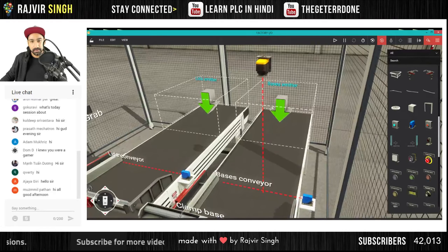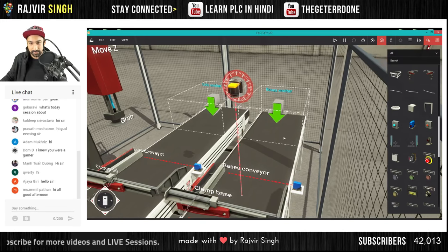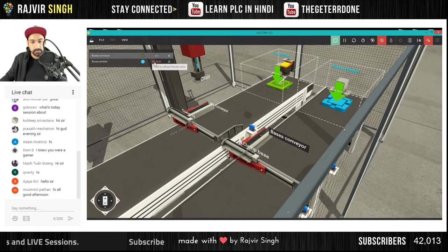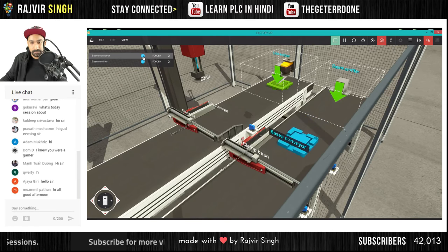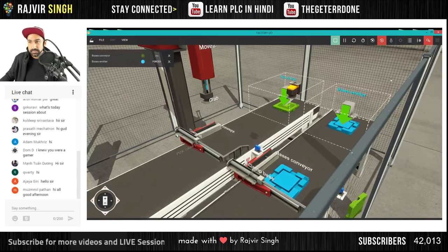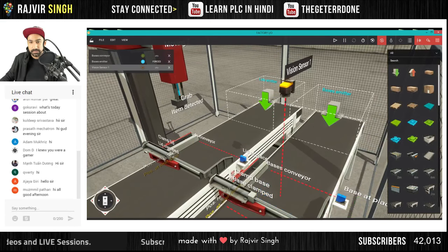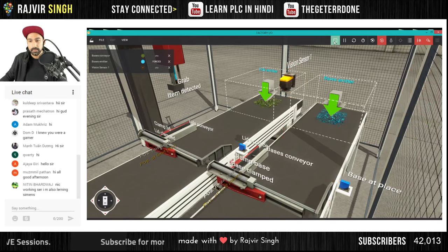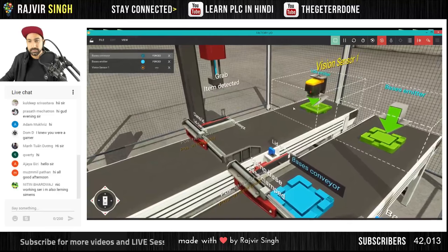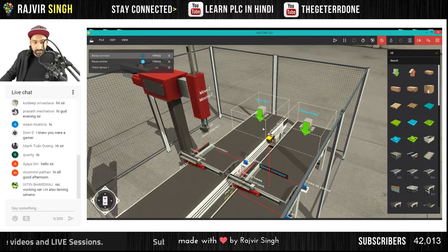The camera position depends on where you want it to sense the object. You can position it where the object will be aligned. Let me take an example - I take out a box and run the conveyor. The conveyor is coming. Now let me stop the conveyor and check what the sensor says about this object. The vision sensor is here but it's not sensing the object - it's probably too high.